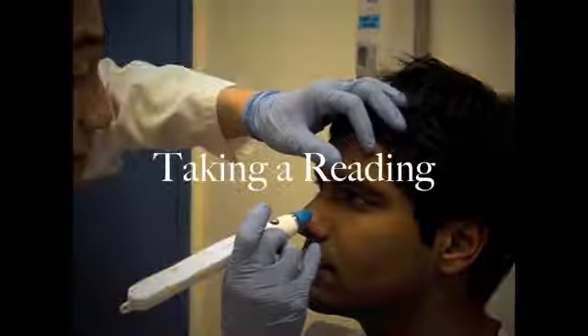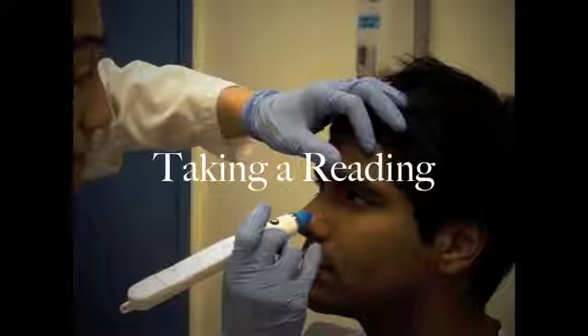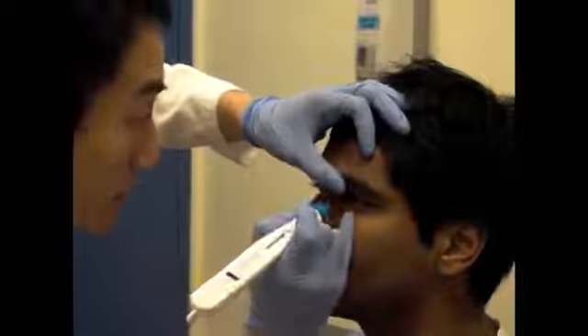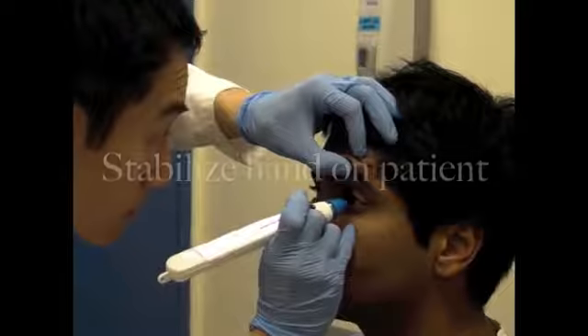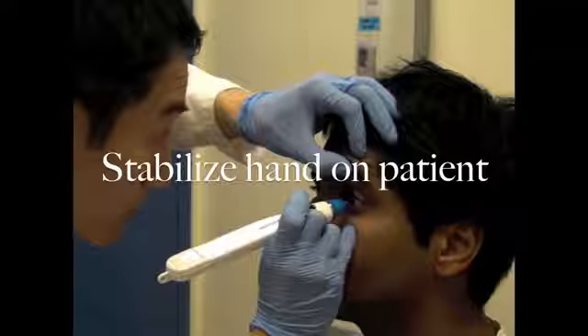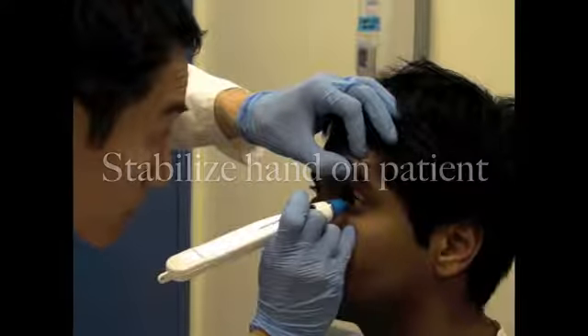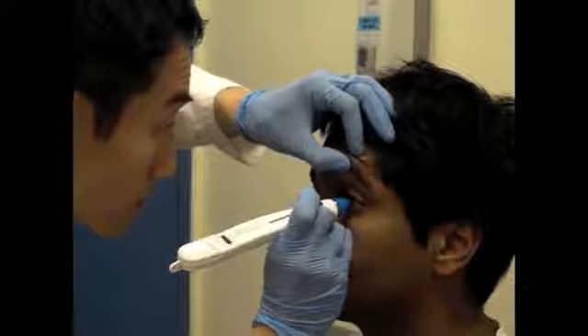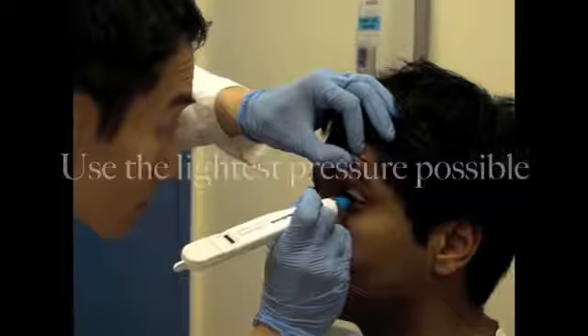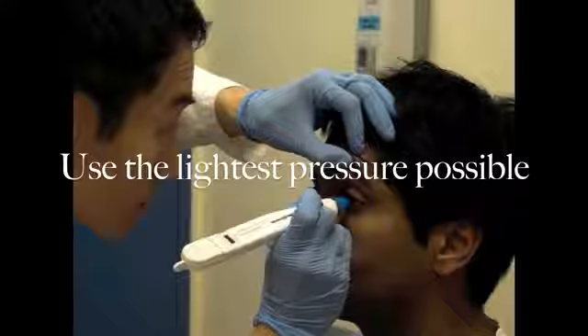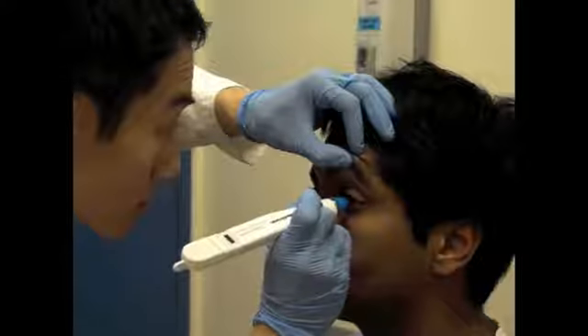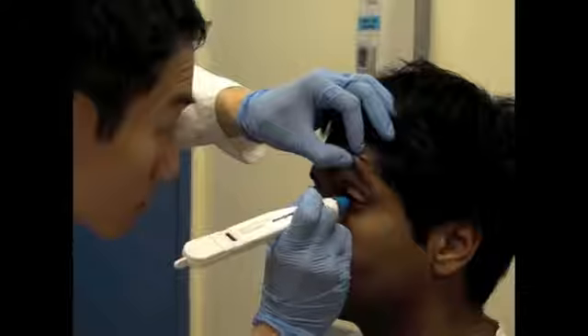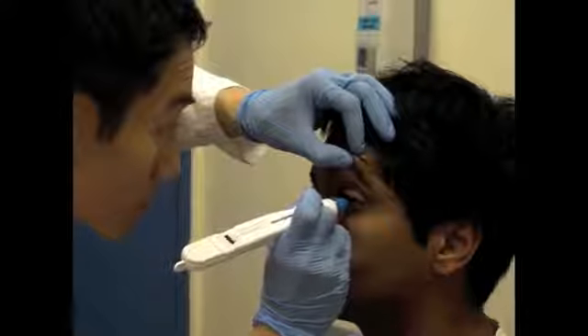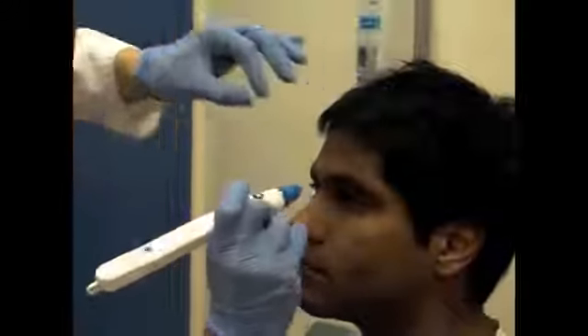Have the patient visually focus on a stationary target like your ear. Without pressing on the eyeball, gently lift up the upper eyelid. Brace your 5th finger or heel of your hand on the patient's cheek for stability. Remember to take measurements by touching the probe tip to the cornea, using the lightest and briefest pressure that will obtain a reading. Repeat this several times, as you will hear some smaller clicks before a louder beep. This louder beep indicates that the tonometer has taken enough measurements to average into a final reading.